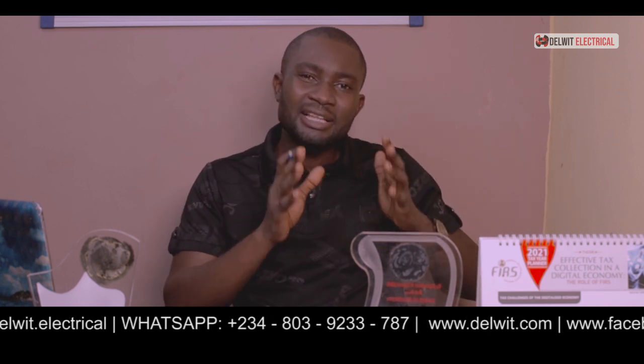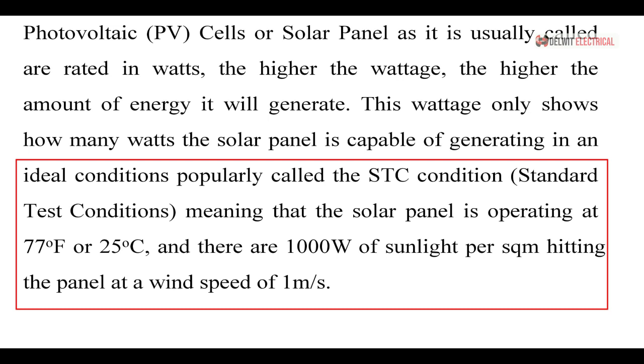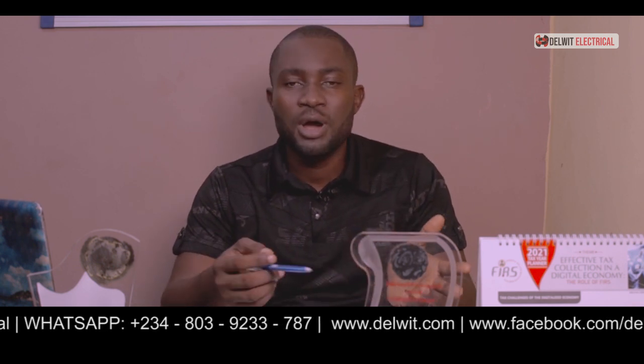Our discussion today is to talk about the sizing of your photovoltaic panels. The wattage rating on the panel is based on Standard Test Condition, or STC. As shown on our screen, STC conditions require: the test must be carried out at 77 degrees Fahrenheit or 25 degrees Celsius, there must be 1000 watts of sunlight per square meter hitting the panel, and the wind speed must be at one meter per second. When you don't always have these exact conditions, that is why a panel rated at 320 watts is approximate — it is rated at standard test conditions.